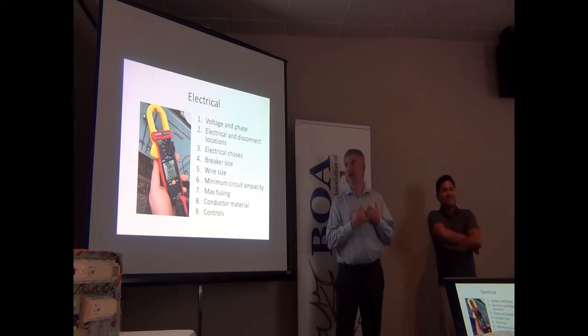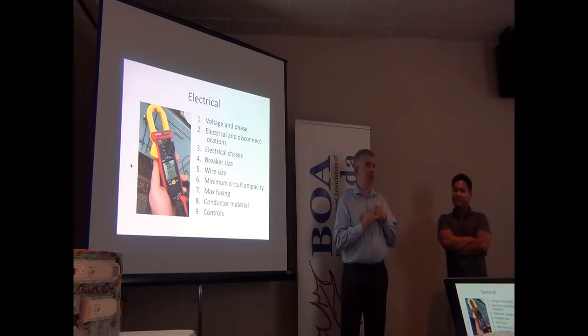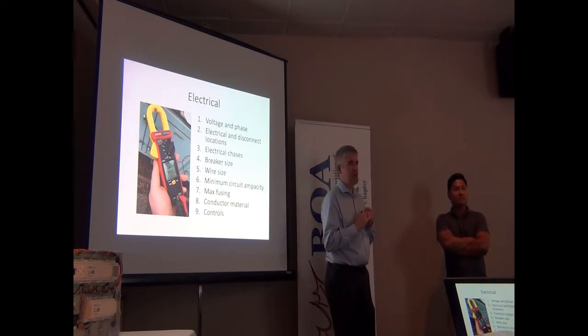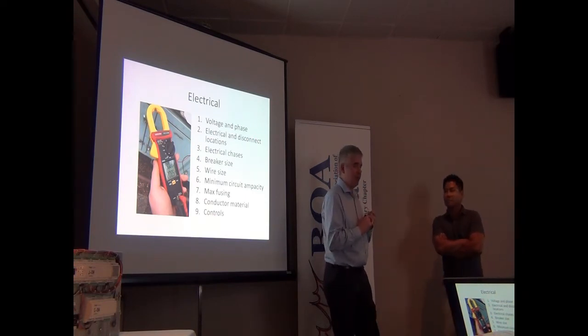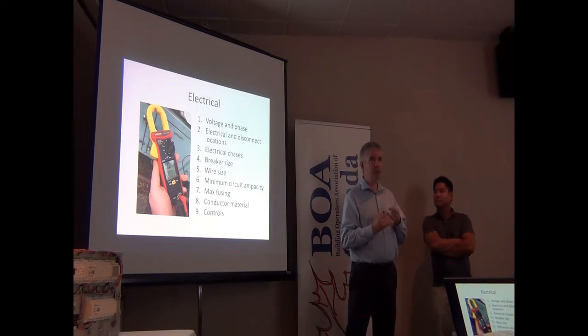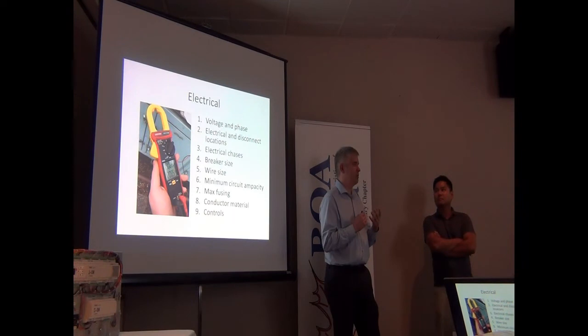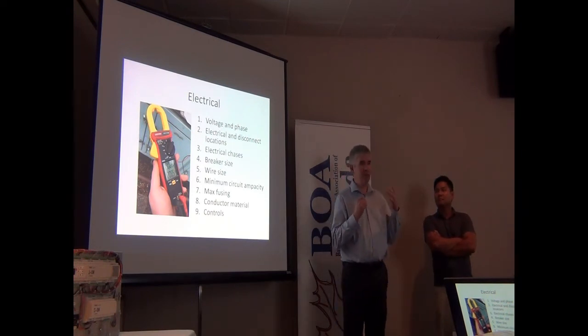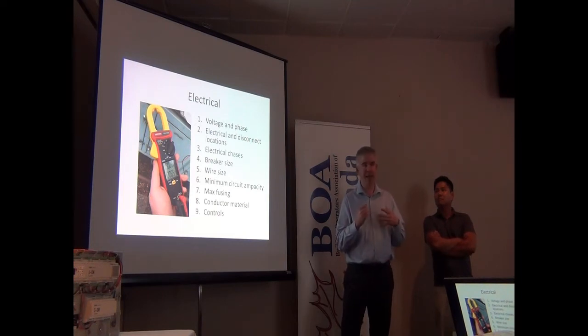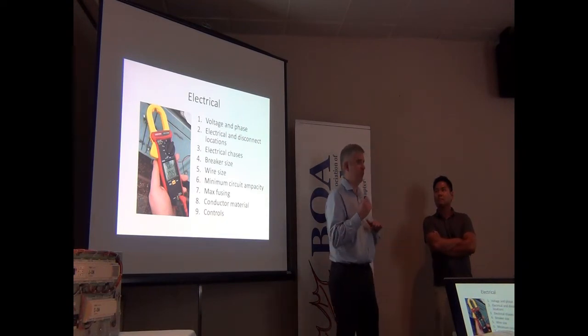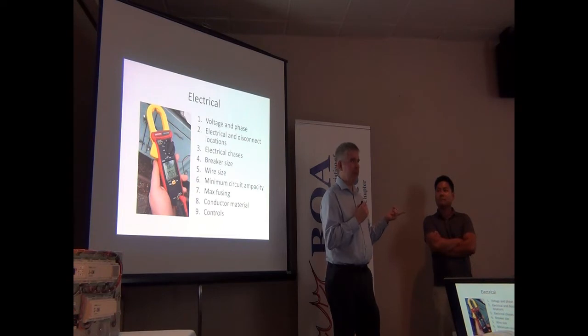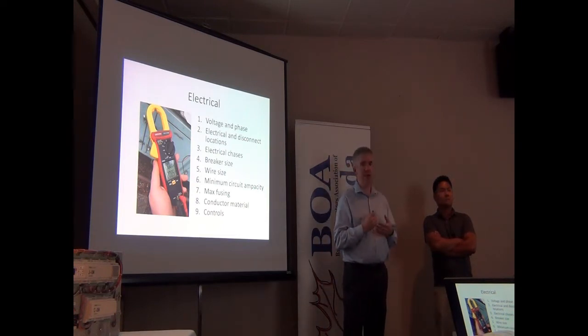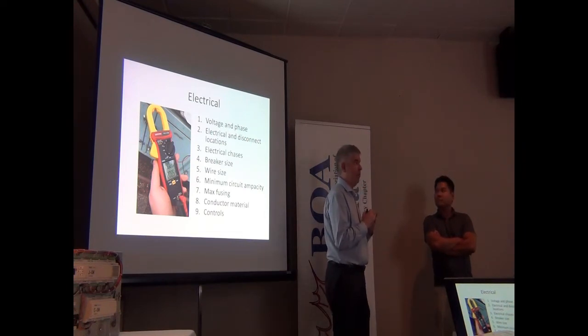And the other one was electrical considerations. So probably the biggest one is amperage. Is the amperage of your appliance going to change? This could happen for a couple of reasons. One, with efficiencies in air conditioning that are now required, and compressors that weren't nearly as good. So reciprocating compressors from the 80s or 90s, replacing them now with a scroll compressor on a unit that has condenser fans that have lower horsepower, bigger coils, I've seen it where suddenly your breaker size drops with a BTU for BTU replacement. That can be a really big deal if your contractor hasn't looked at it, going, we have a panel that's from 1950 that has a breaker in it that we can't just replace off the shelf anymore. So looking at whether your electrical load is changing for being smaller can actually happen for that reason.